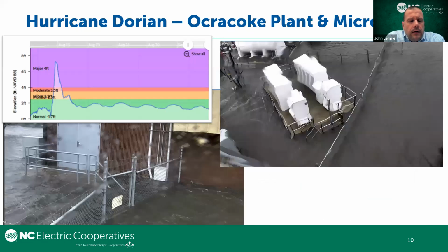So the second lesson at our Ocracoke microgrid that I want to talk about is to know your environment. You can see pictures here of flooding. Back in 2019, Hurricane Dorian came through and we had record flooding on Ocracoke Island. When we designed the project, and you see the photo of the batteries, those batteries are up on a 4-foot tall concrete platform. And you can see how close the water is to those batteries. The flooding that we experienced during this event reached up almost to 6 feet. And so the flooding caused power outages and caused an outage at Ocracoke Island.